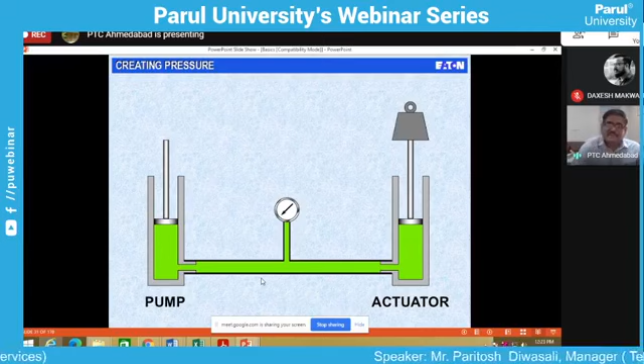When the flow of fluid is restricted, pressure is built up. As you can see in the previous slide, no flow is restricted, no pressure is built up. But when flow is restricted, pressure will build up. So the very first fundamental thing we have now understood is that the pressure is not generated by the pump. The pump is responsible for creating flow, but pressure is generated due to restriction or resistance to the flow. That is what one has to understand.